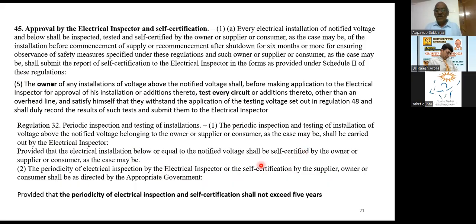So why I'm saying this: the periodicity shall not exceed 5 years. Can we maintain this periodicity? Every installation should be inspected within a period of less than 5 years. Is it possible in this major country where 140 crore people are living and we are having 100 crore service connections? It is quite impossible. That's why the government and the regulatory authorities have introduced the term competent electrical safety engineers as per regulation 6, but unfortunately it is practically remaining unimplemented and missing.